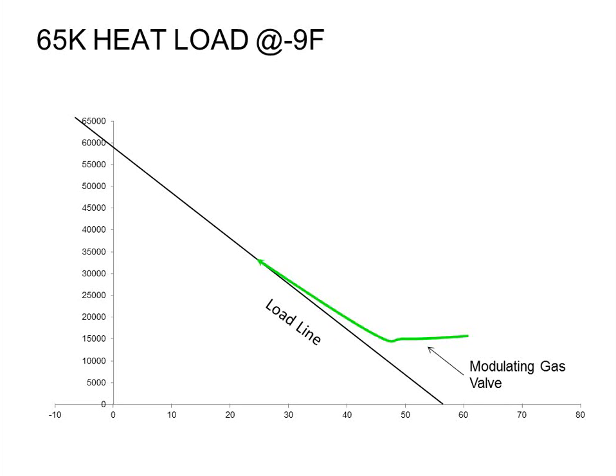You were asking for 72 degrees. Now you walked up to it and bumped it down to 68. Well, it's going to look at it and calculate and then say, well, I'm actually 4 degrees hotter than you want, so I better start modulating down. Then he's going to modulate down to 40% and say, dang, I'm still way hotter than you wanted. I'm going to have to shut off for a while and let that thing drift down to 68 degrees in the house, then turn it back on and modulate from there.